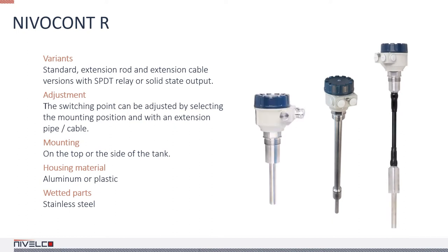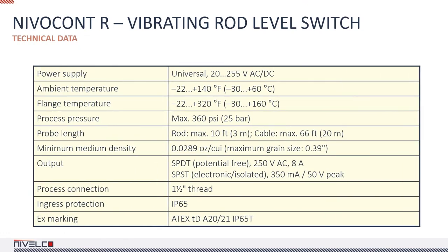There are numerous options, like an extension rod or an extension cable for the probe, and the output can either be an SPDT or a solid-state relay. The device cover is either aluminum or plastic, and the wetted parts are made of stainless steel. The highest range temperature is 320 degrees Fahrenheit, and the maximum process pressure is 360 PSI. The device has an ATEX variant.